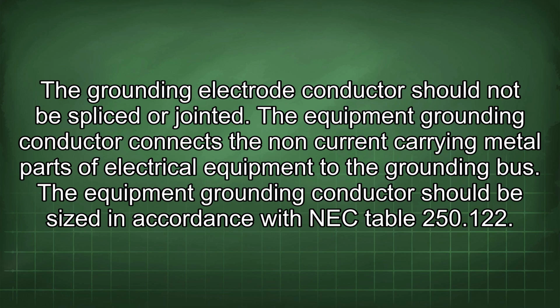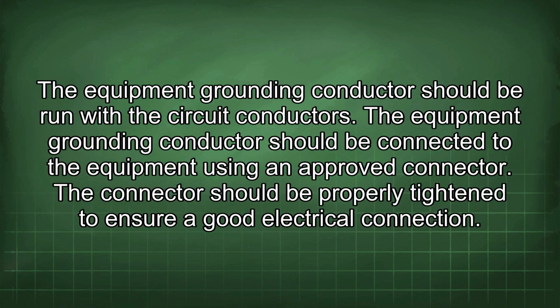The equipment grounding conductor connects the non-current carrying metal parts of electrical equipment to the grounding bus. The equipment grounding conductor should be sized in accordance with NEC Table 250.122. The equipment grounding conductor should be run with the circuit conductors. The equipment grounding conductor should be connected to the equipment using an approved connector. The connector should be properly tightened to ensure a good electrical connection.